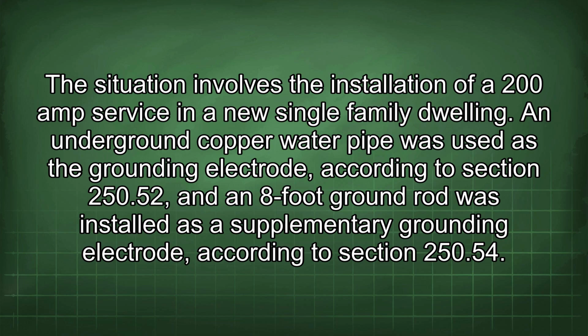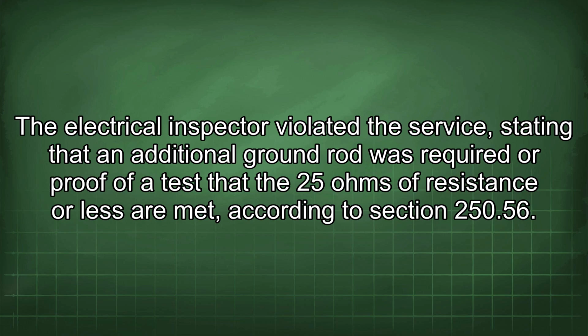An underground copper water pipe was used as the grounding electrode, according to Section 250.52, and an 8-foot ground rod was installed as a supplementary grounding electrode, according to Section 250.54. The electrical inspector violated the service, stating that an additional ground rod was required or proof of a test that the 25 ohms of resistance or less are met, according to Section 250.56.